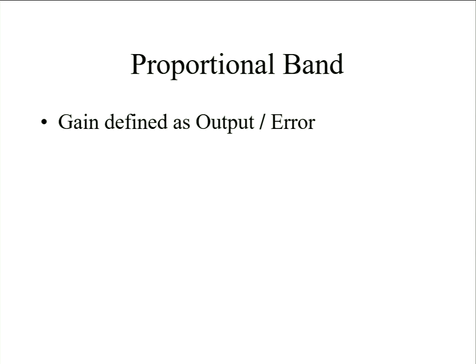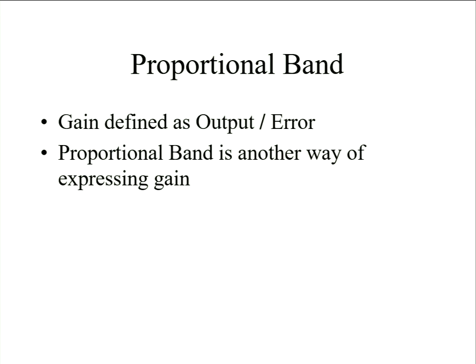What you've got to understand is it's described as a percentage. So the bigger the gain, the smaller the proportional band, which I never found intuitively obvious: a 4% proportional band is a very high gain. That's a big number, high gain. But it's still used in many cases, because what high gain means is you would get a lot of change of output driven for a small error, so it's a high gain system.